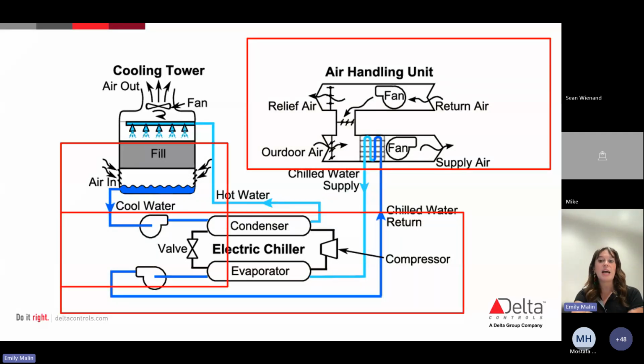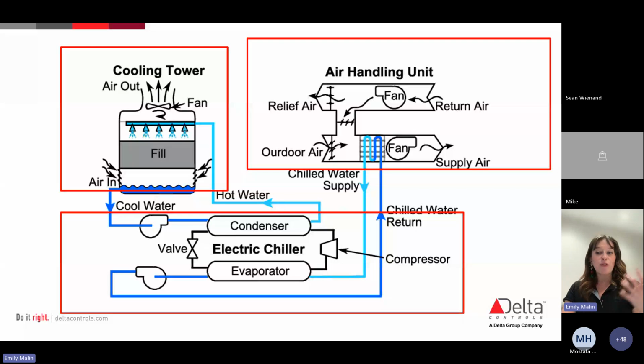Same thing with our cooling tower. Once the water is coming out of the chiller or coming to the chiller, you're basically sensing that temperature on both sides of it. If you're sensing that your water is too warm, your control system is going to start to speed up the cooling tower fans in order to blow more air and to cool that water faster. So again, all of this is just to say that you're seeing how each one of these interdependent systems is working together to make sure that we're achieving that desired set point inside of a zone without using more energy than we actually need to.